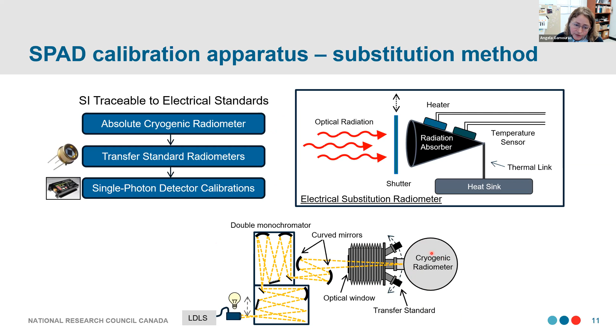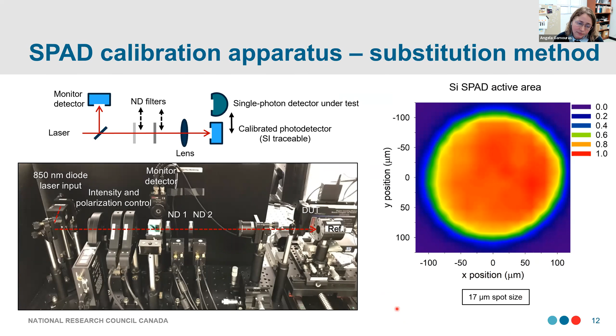So one major challenge with calibrating SPAD detectors is that their active area is very, very small, about 150 microns or so. And so we actually have a three-dimensional stage for the detector under test that actively aligns the detector to the center position on the active area. So here you can see a spatial uniformity map of this detector under test, for example. And so it's important to consider your spot size of these detectors so that you're underfilling them, you're not missing any photons.